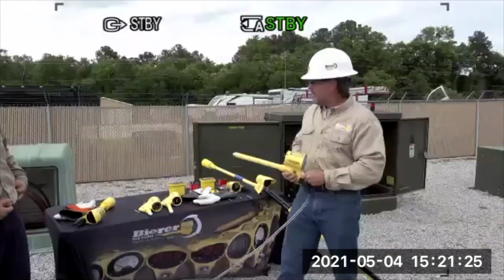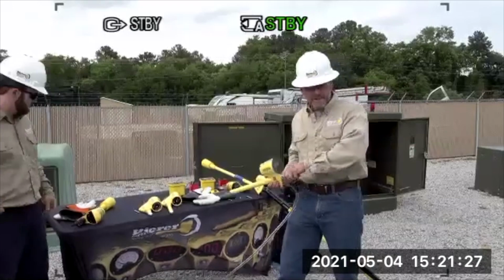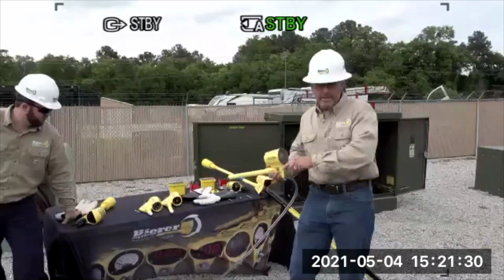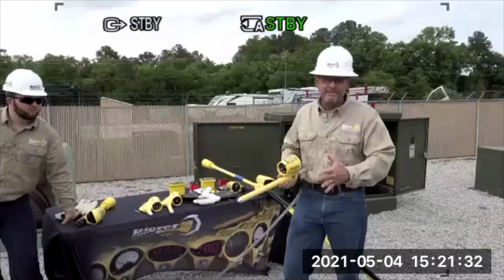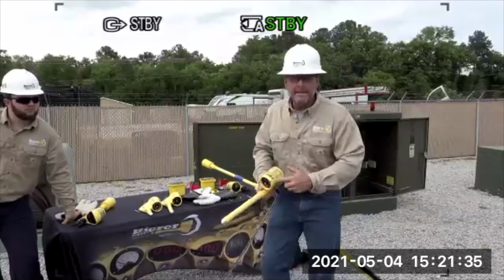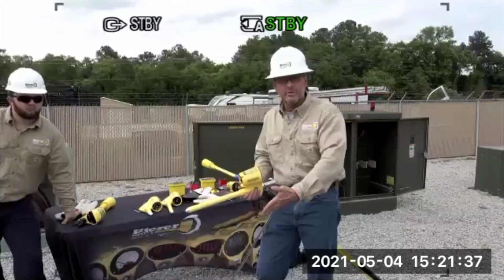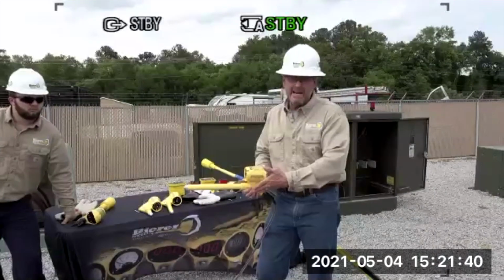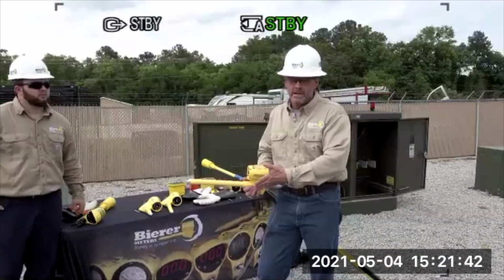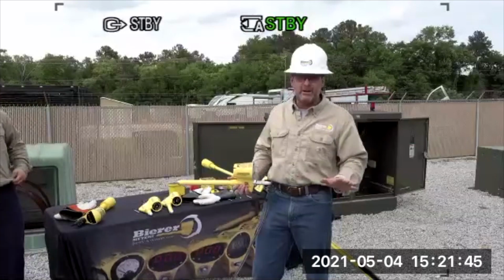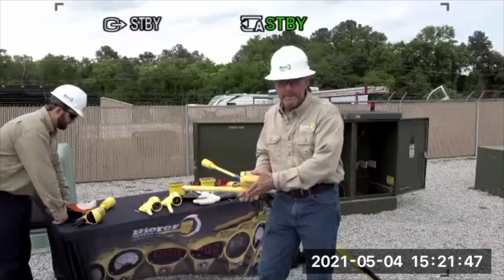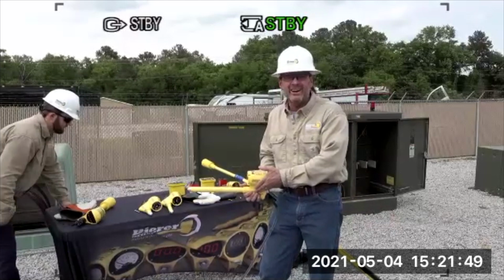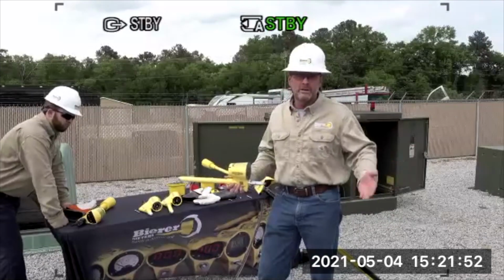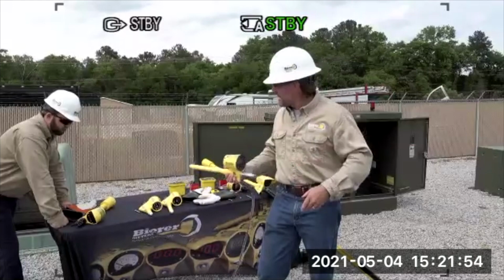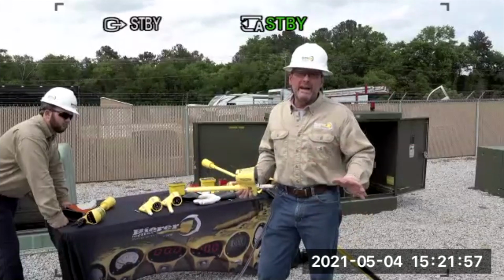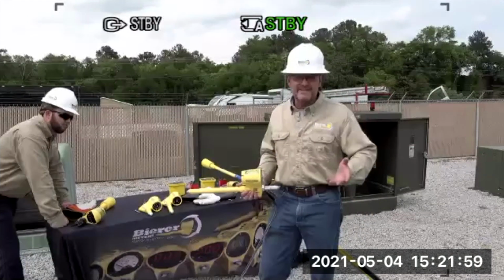Also, from time to time you'll be using the tool, wireless or corded, in a tight vault or tight cabinet, and the meter head may be close to the cabinet, a potential ground plane. A lot of guys have stories and pictures of using their tools, and it doesn't matter whose tools they are, where the meter head is actually laying on a potential ground, maybe a neutral or a cabinet. You don't ever want to use anybody's tools in that scenario.